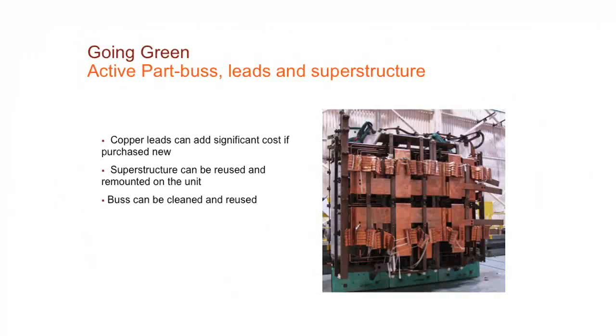The second portion that is typically reusable and recyclable for transformers is the superstructure and the bus and the leads. There's a lot of copper inside of this transformer, and the superstructure itself and the leads itself actually is typically reusable. You're saving a lot of money by reusing these leads. Our team can crimp or braze these leads. If there are any problems with the leads, we can replace several sections of it if needed, but the majority of the time we are able to reuse the whole superstructure or all the leads. They can also be cleaned off using that non-conductive solvent as well.